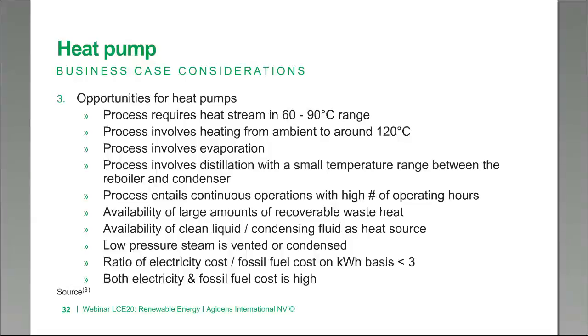Clearly you need to have a source temperature, and the higher the amount of recoverable waste heat you have, the more available energy you have to upgrade in the heat pump. If you have clean liquid or condensing fluid as a heat source, then you can go for a heat pump. If you have a lot of low pressure steam that is vented or condensed, that also presents an opportunity. It's also important to look at the cost of electricity versus the cost of fossil fuels. Traditionally you would want a ratio where electricity cost divided by fossil fuel cost on a kilowatt hour basis is less than three. If electricity becomes more expensive, you will end up gaining little or no value from the heat pump unless you're dealing with very high COPs.